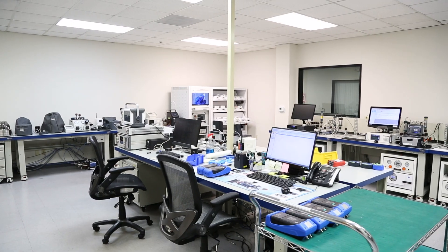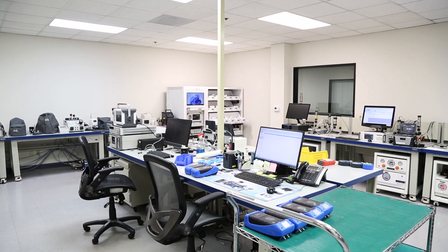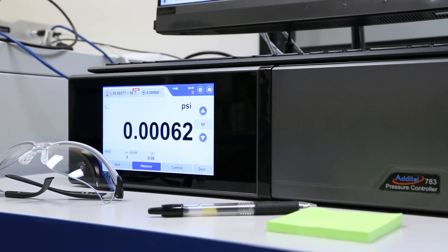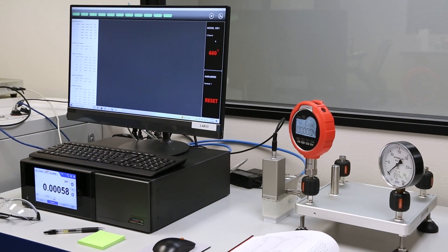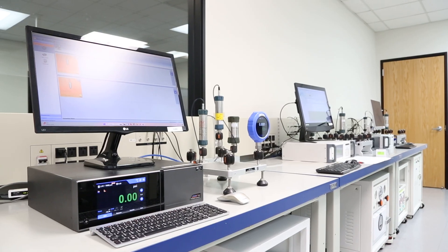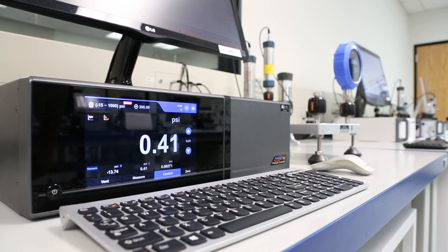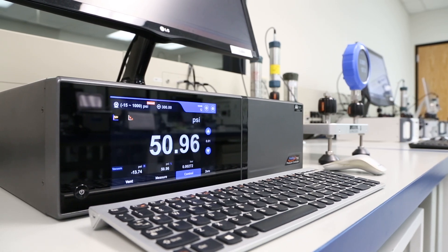Now that we've gone over a field calibration, let's look at a laboratory calibration. For most devices, calibration labs will use a pressure controller and reference module setup, as it allows for multiple DUTs to be connected to a manifold at once. These pressure controllers can often be connected directly to calibration software in order to automatically upload test results and generate calibration certificates.